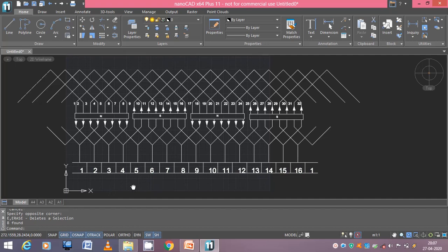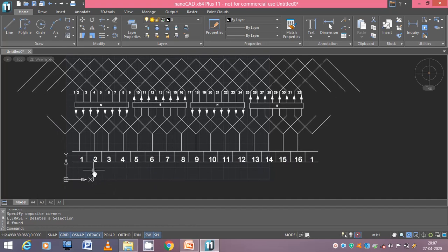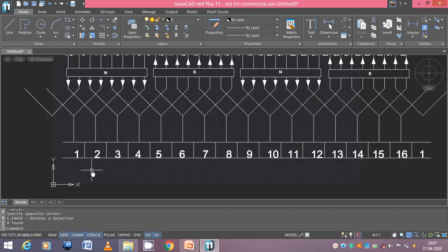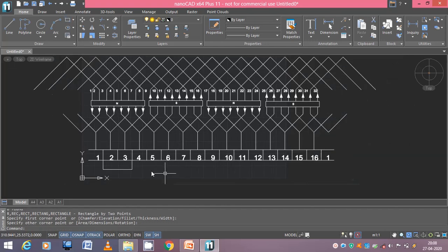Under each pole there will be 2 locations for the placement of brushes, because it is a duplex lap winding diagram. That is the difference, right? In all the problems, the two commutator segments will always be adjacent. Therefore I will place brushes together at commutator segments 2 and 3.